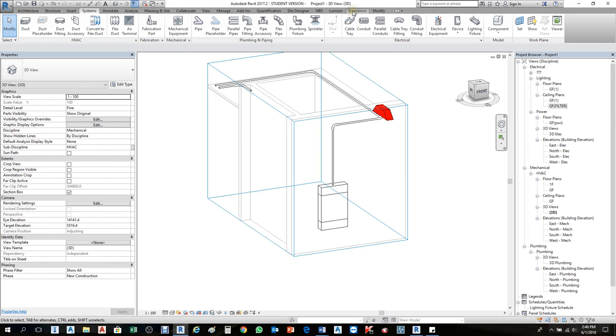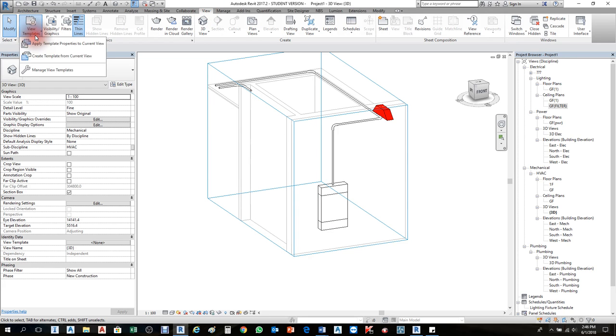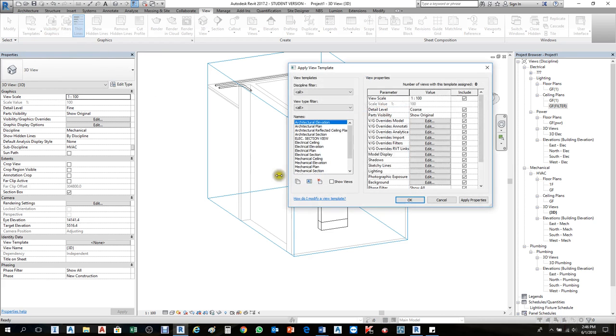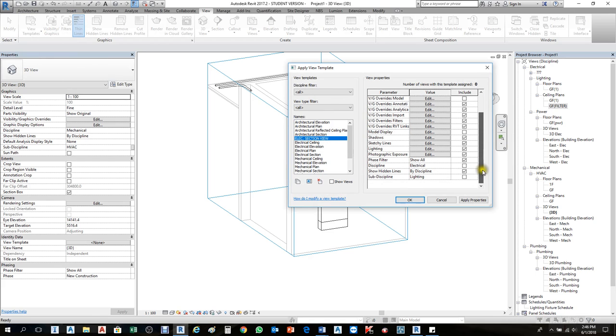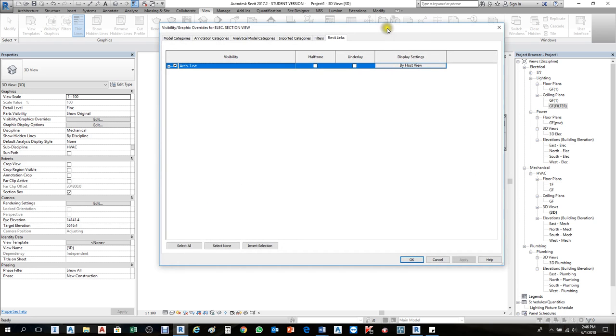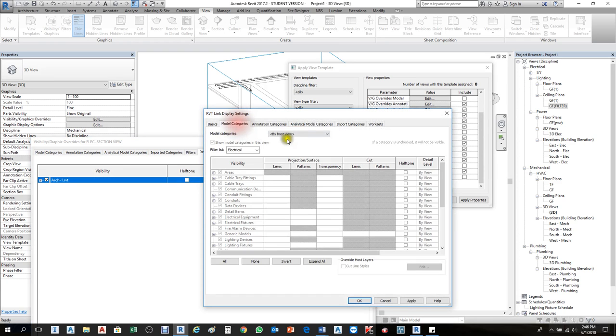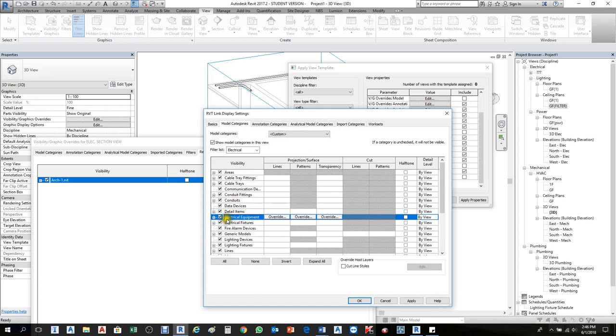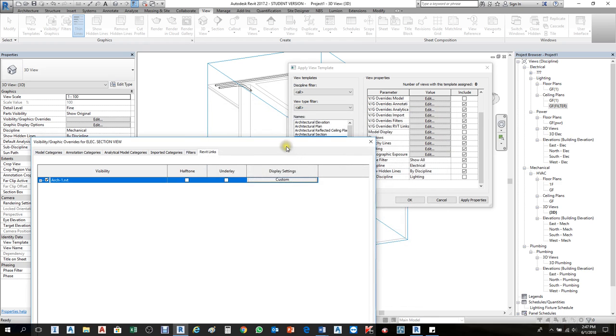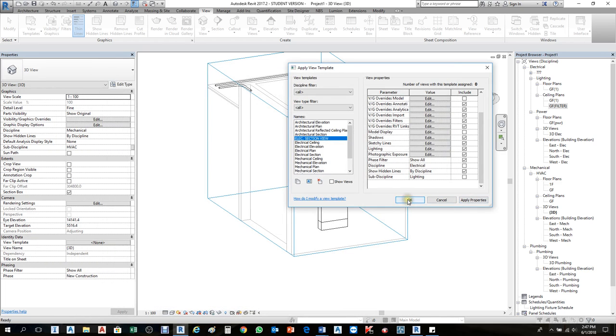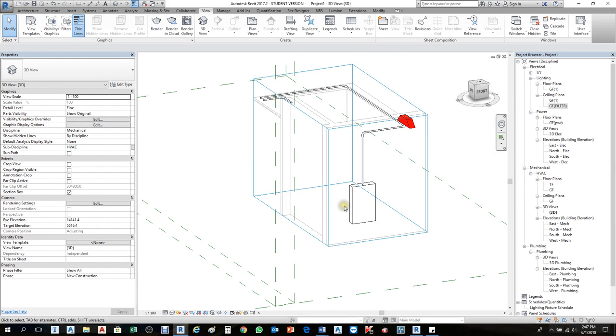Apply a View Template — for example, an Electrical Section View template. Inside the template, set the linked file's Electrical Equipment to hidden so it doesn't interfere. Go to the Visibility settings, set it to Custom, and under the link, hide Electrical Equipment. Apply the template. From now on, any section view using this template will automatically hide linked file electrical equipment.